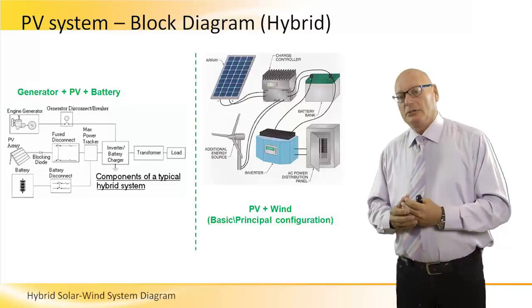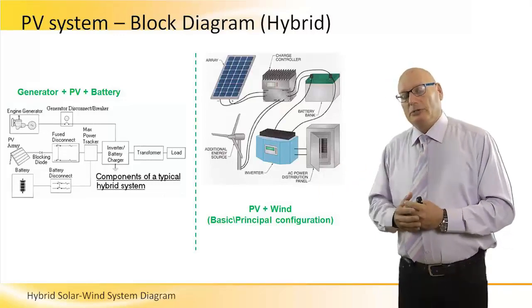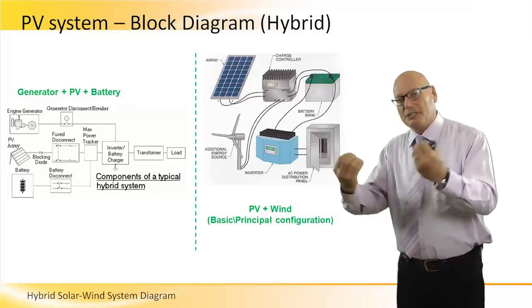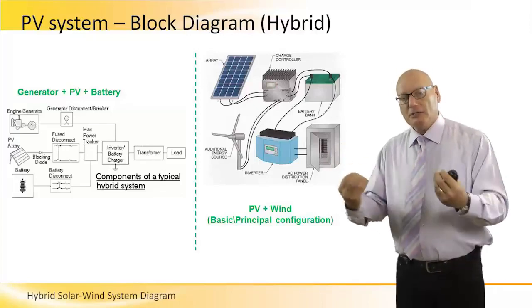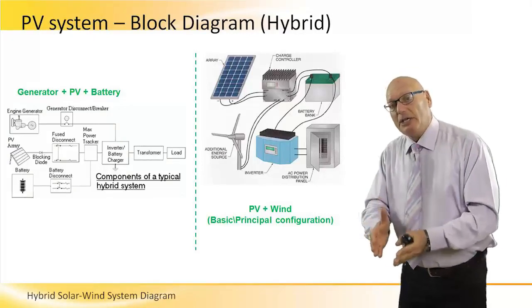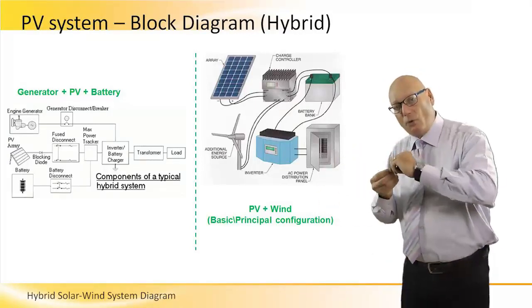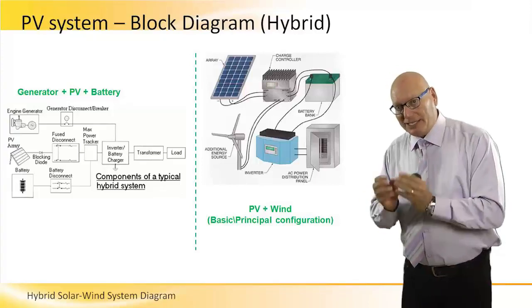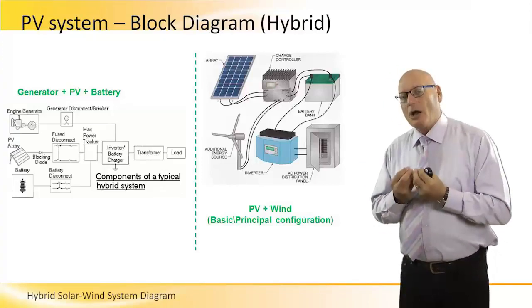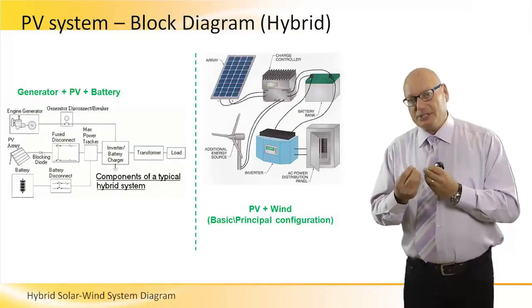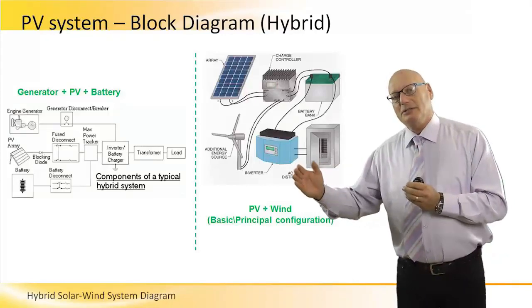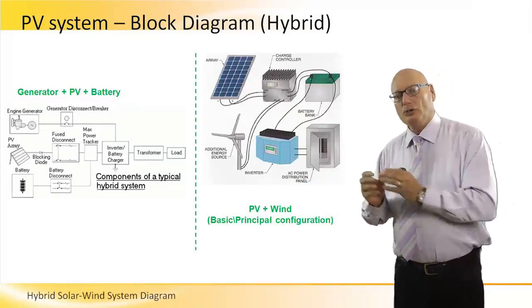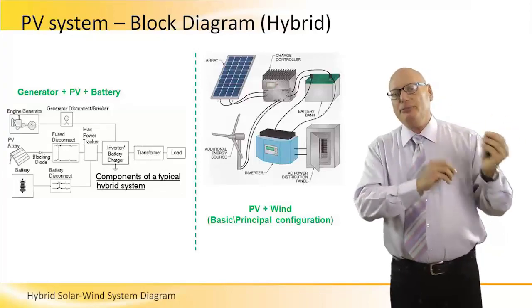At night there's no sun at all — there might be wind or might not. During the day, wind and sun together. So at any given moment of time, the charge controller sees two inputs and they vary. Still, it should control the charging of the battery with well-defined characteristics and a well-defined equation. The charge controller needs to look at the two inputs, optimize their characteristics at any given moment, and send DC output for charging the battery. The battery should not be aware of what is happening at the input to the controller.